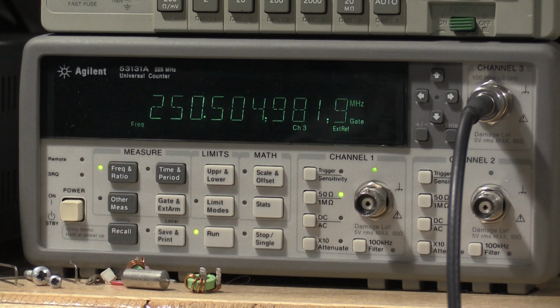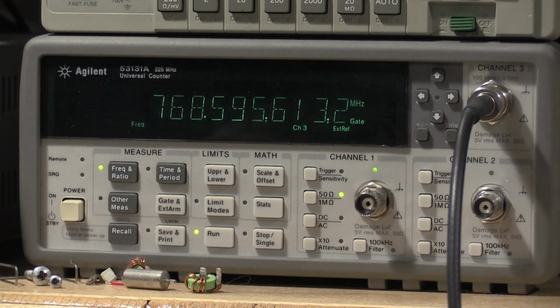Here's our 250 megahertz, so that's in spec as well. I'm allowed 1.25, and that's 0.5, so perfect. Let's check the high range. Well, that's supposed to be 750, so that is not. Ugh. This one's not going to be nice.